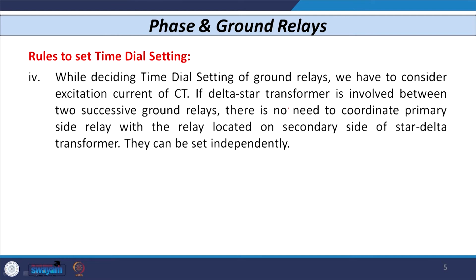When a star-delta transformer is involved between two successive ground relays, you can set both relays independently — you can even set instantaneous operation for both. We will discuss later why there is no need for any such rule when a star-delta transformer is involved.